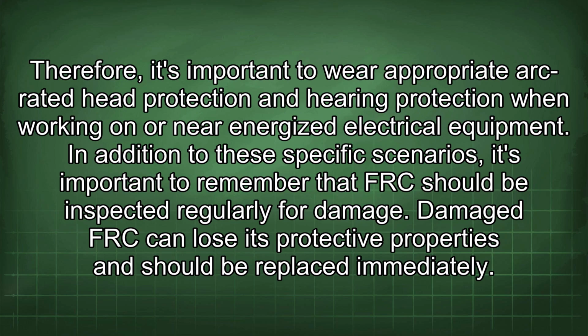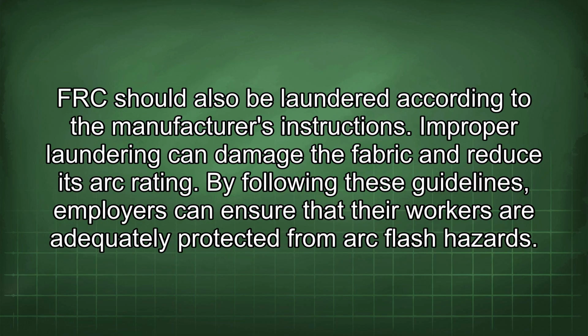In addition to these specific scenarios, it's important to remember that FRC should be inspected regularly for damage. Damaged FRC can lose its protective properties and should be replaced immediately. FRC should also be laundered according to the manufacturer's instructions. Improper laundering can damage the fabric and reduce its arc rating.